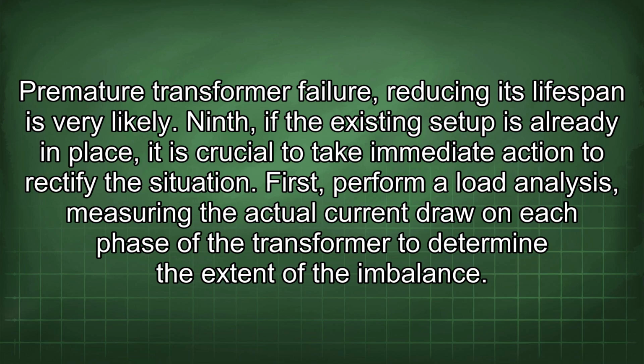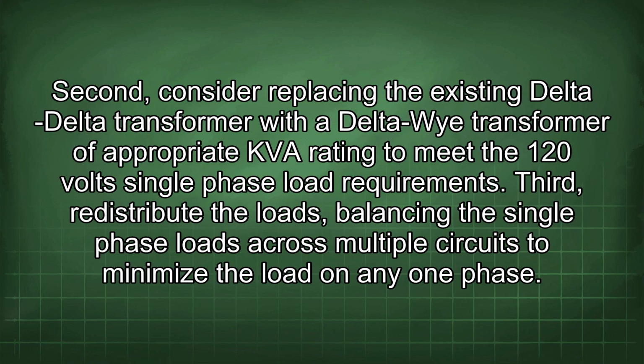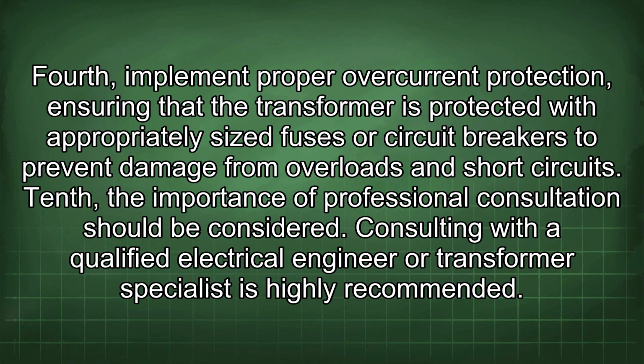Ninth, if the existing setup is already in place, it is crucial to take immediate action to rectify the situation. First, perform a load analysis, measuring the actual current draw on each phase of the transformer to determine the extent of the imbalance. Second, consider replacing the existing delta-delta transformer with a Delta-Wye transformer of appropriate kVA rating to meet the 120 volt single-phase load requirements. Third, redistribute the loads, balancing the single-phase loads across multiple circuits to minimize the load on any one phase. Fourth, implement proper overcurrent protection, ensuring that the transformer is protected with appropriately sized fuses or circuit breakers to prevent damage from overloads and short circuits.